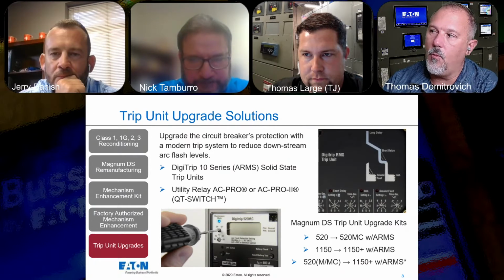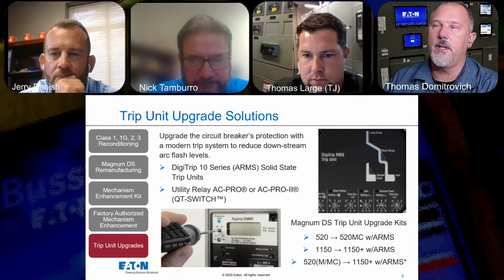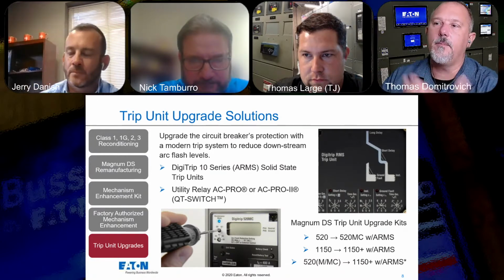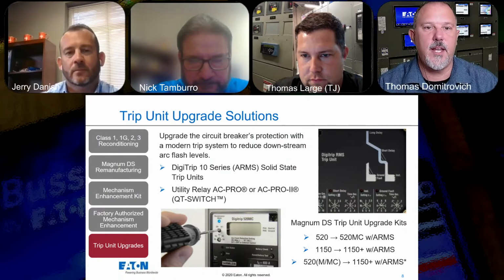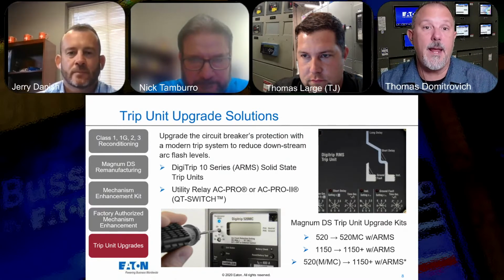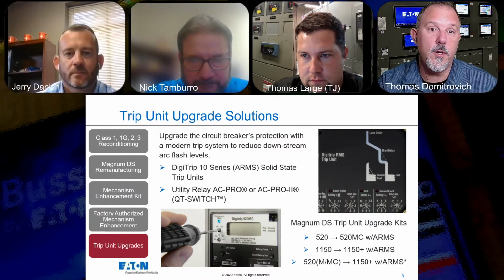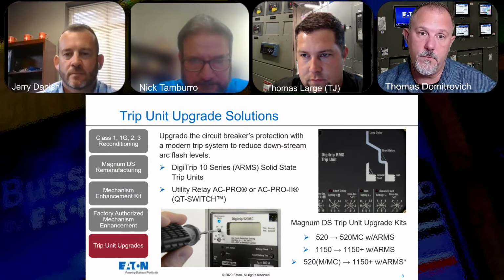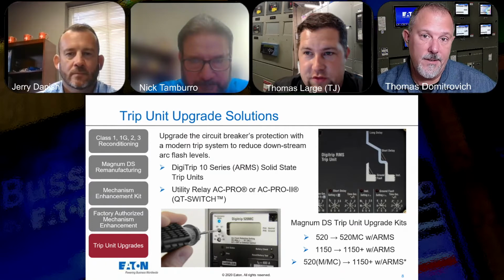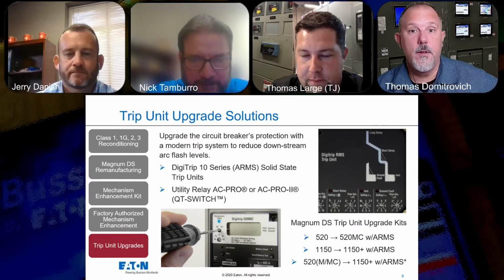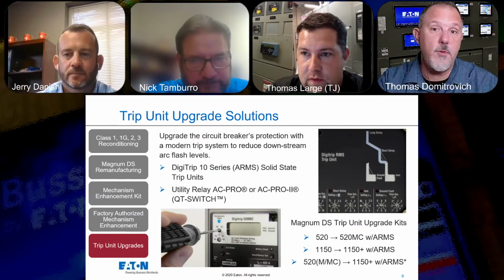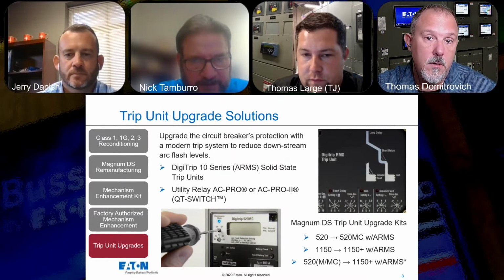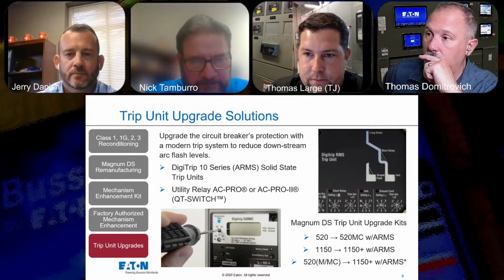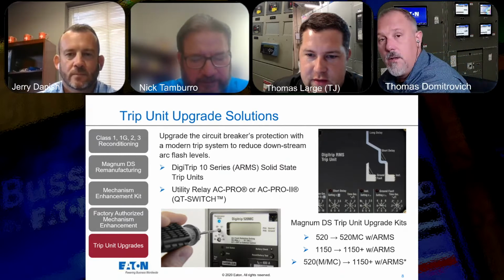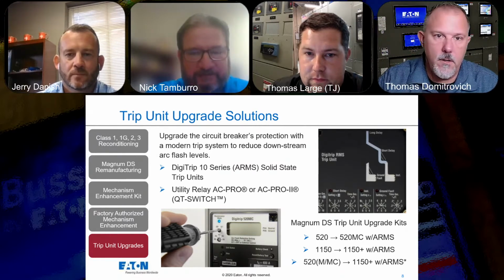So what's the extent? Are there cases where you cannot put these trip units on, or add this to, an older breaker, or can you pretty much do that to any breaker? Pretty much any breaker. Really? Okay. Any manufacturer. So can I put this trip unit on like a GE breaker? Yes. Wow, that's pretty cool. Yeah. Whatever there's a retrofit kit designed for, yes.